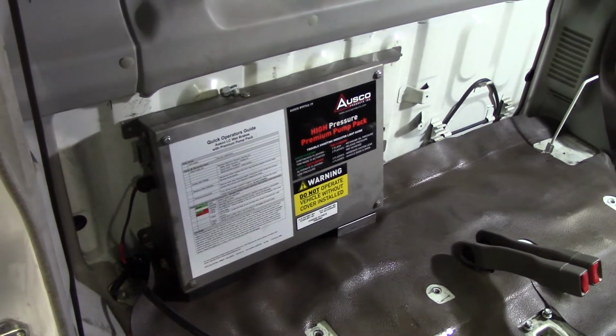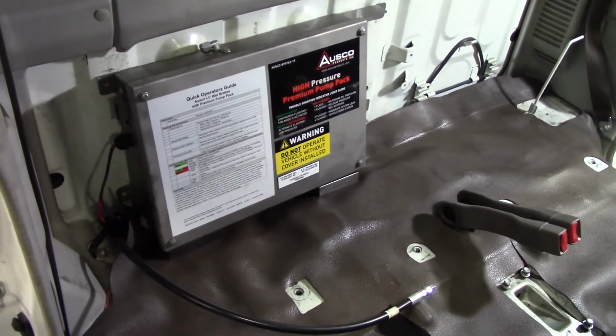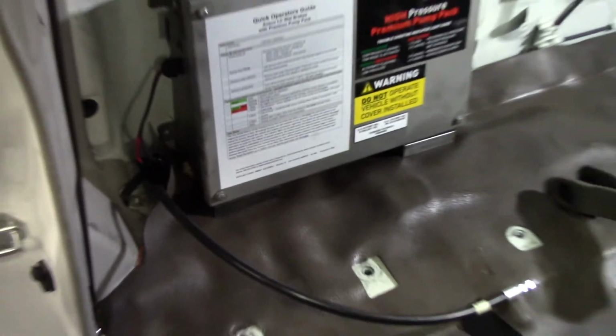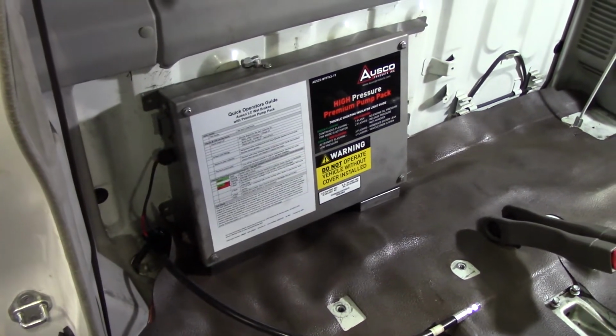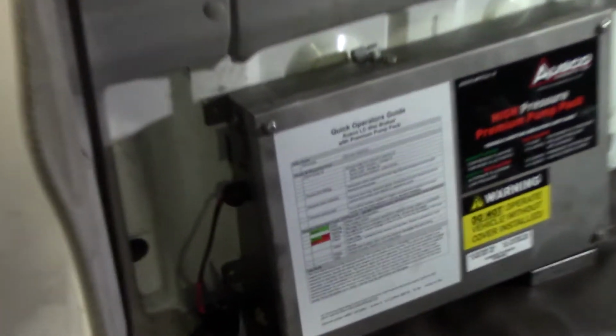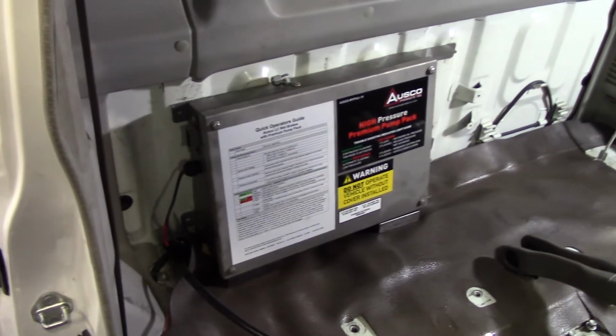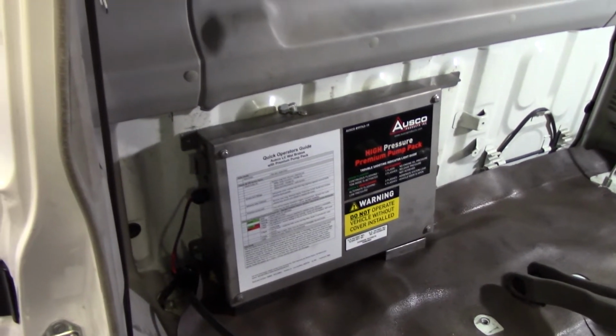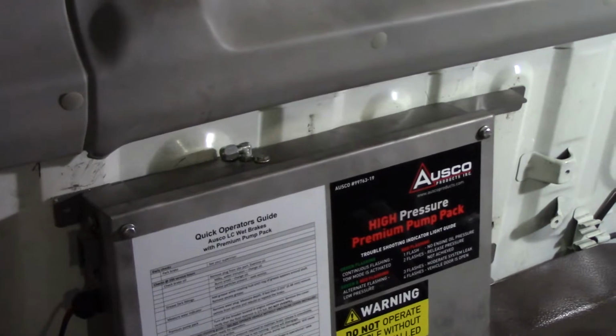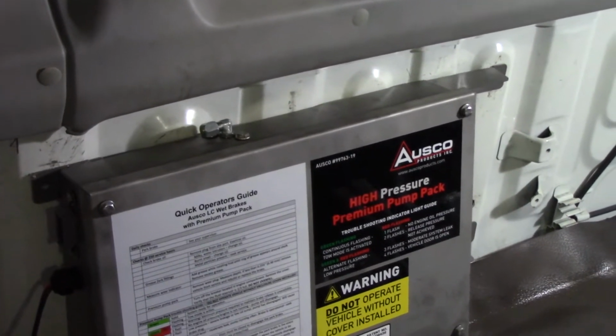The next thing in line is grabbing some 25mm spacers. As you can see, I've got a couple of metal blocks under our pump pack on the back wall. Those are used so we know we have enough clearance for our wiring harnesses that plug into the side of the pump pack. They're not plugged in yet, but they'll run underneath that pump pack. So you want to make sure you have clearance under the box, and also make sure it's level, because there will be fluid in there.